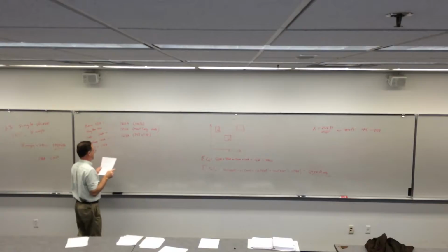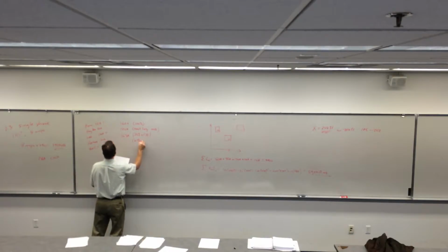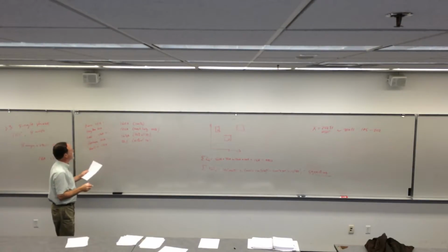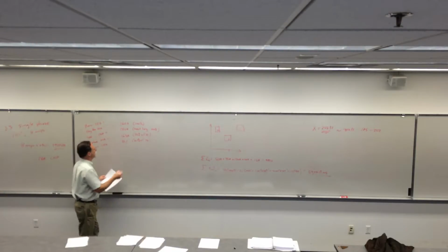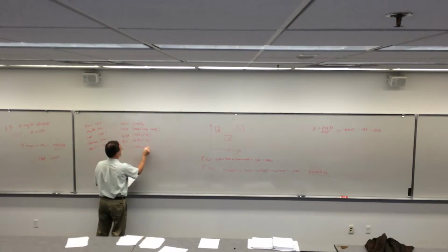The third one is 50 amps, and 65% of that is 32.5. And the fourth is 50% of the sum of all the rest, right? 50% of 15 amps is 7.5.